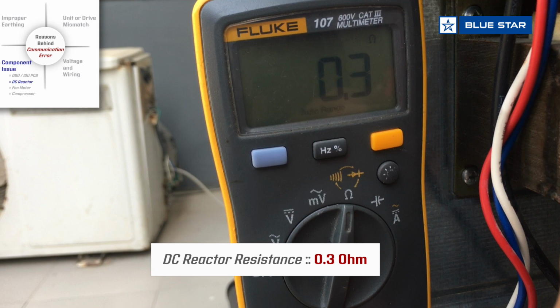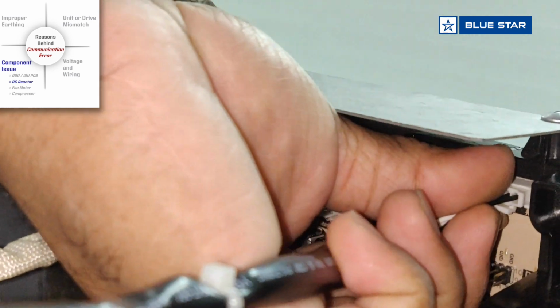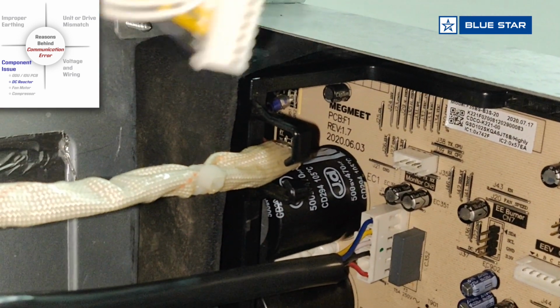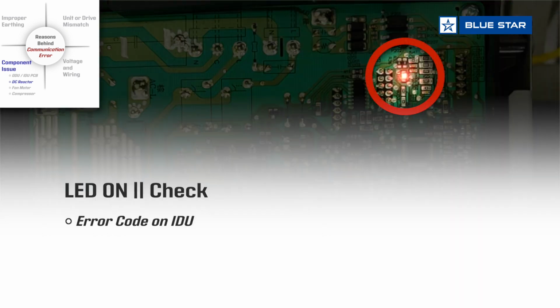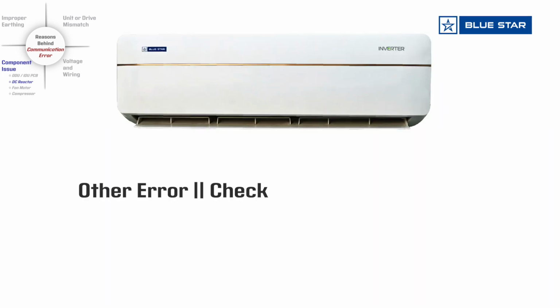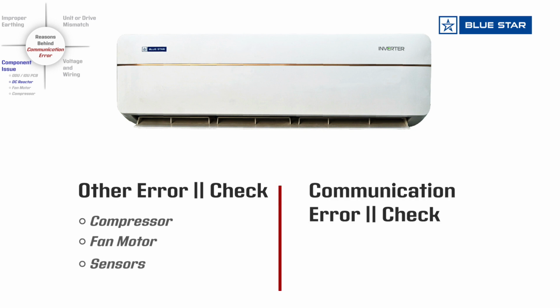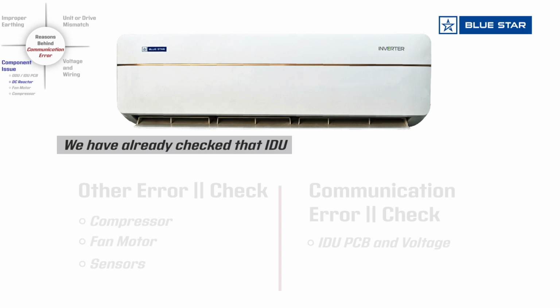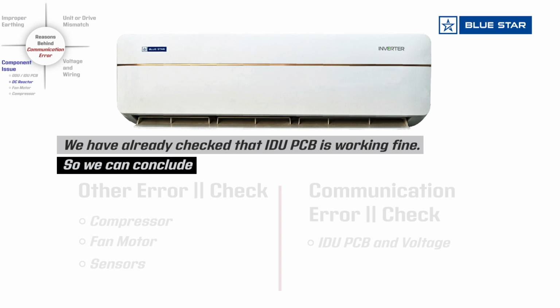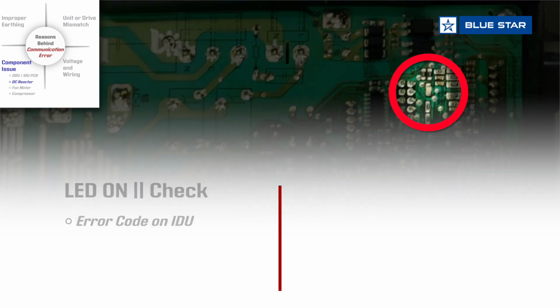If the DC reactor is fine, remove all other connections from the PCB and check if the LED is getting on. If the LED is on, then check if the IDU shows some other error. If yes, then check for faulty components like compressor, fan motor or sensors. If the communication error remains, then check IDU PCB and voltage. We have already checked that IDU PCB is working fine, so we can conclude that ODU PCB is faulty and has to be replaced. If the LED is off, we can conclude that ODU PCB is faulty and needs to be replaced. At the same time, check the reason behind the fault in the PCB.